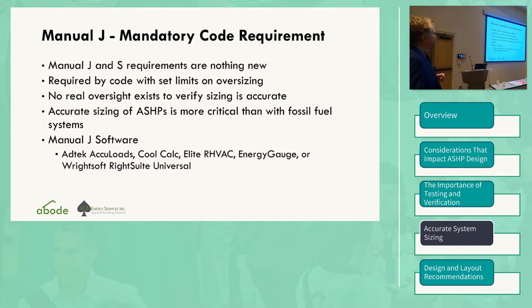Accurate sizing of air source heat pumps is more critical than with fossil fuel systems. Yes, it is - these systems are more precise, they modulate, they're not big beasts that shut off and on and are grossly oversized with an efficiency that doesn't matter. They're much more sophisticated technology and need to be done right.